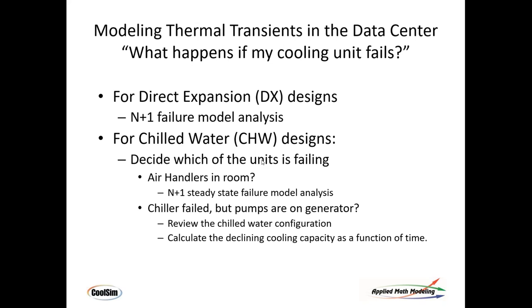Transient simulation in the data center comes up occasionally. We haven't exposed it directly in CoolSim yet, but CoolSim can do a certain amount of it. What we do is perform outside calculations to determine the boundary conditions and then run the solutions inside CoolSim. Let me show you how that's done — this comes from a consulting job done recently.